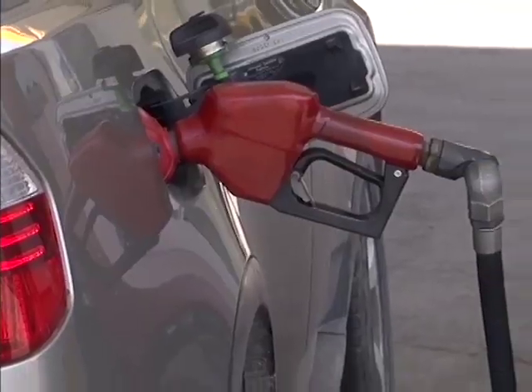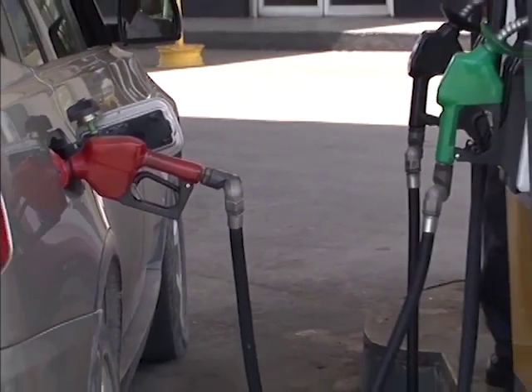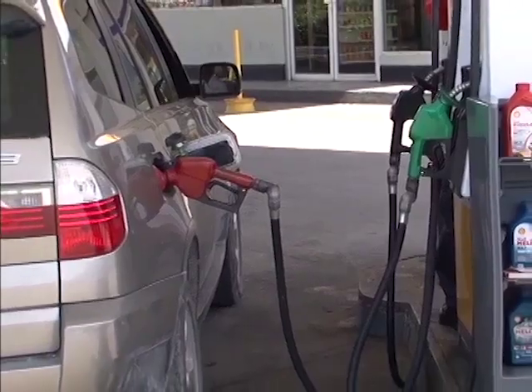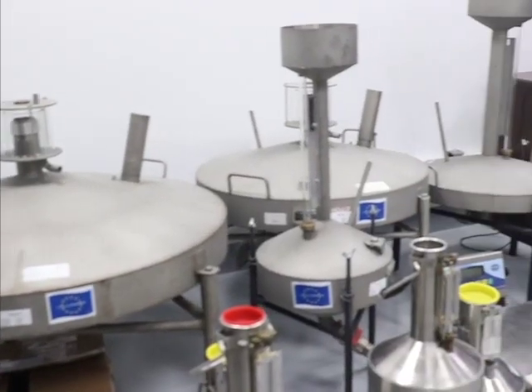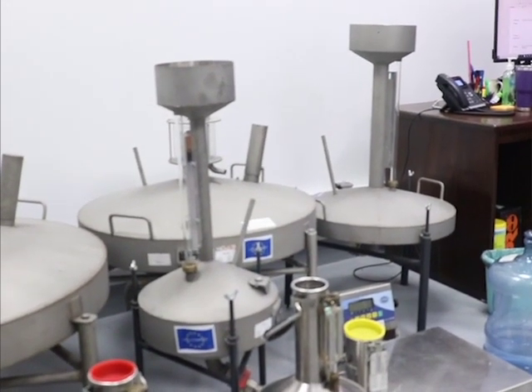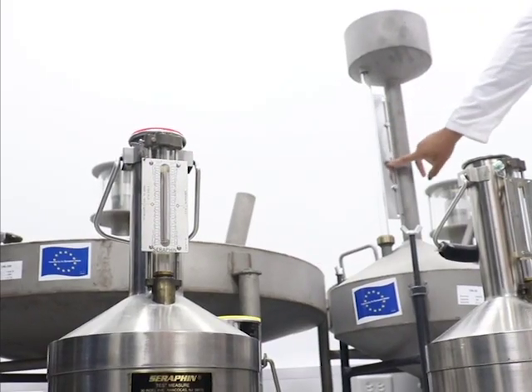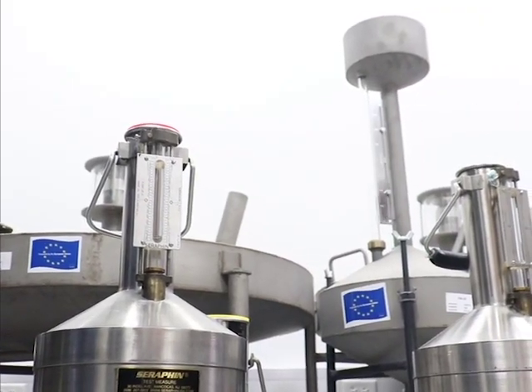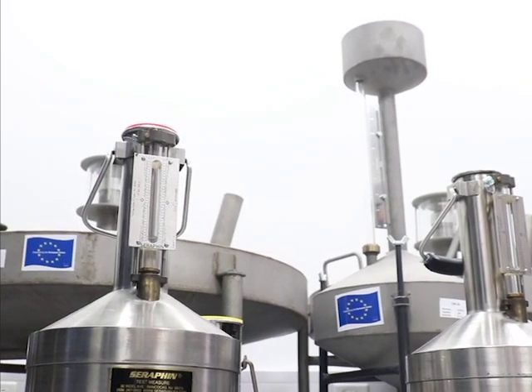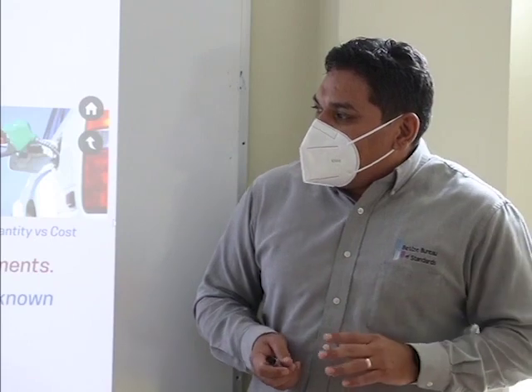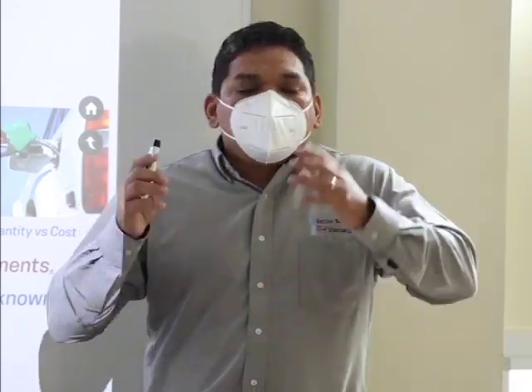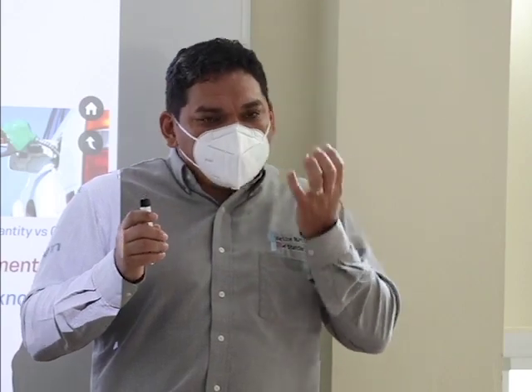Again, through calibration and verification of the equipment. Now there's a difference between the two. When we talk about verification, it's taking a measuring instrument and determining whether or not it's meeting specific requirements, perhaps manufacturer requirements. It's a pass-fail criteria: is it doing what it's meant to do, yes or no? Whereas calibration takes a measuring instrument and compares it with another measuring instrument or reference that we know, or have confidence in what the status of this measurement is.